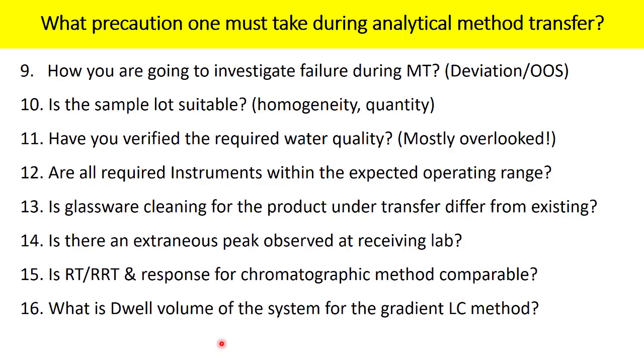And last but not the least. In case if you are operating on the gradient elution mode, the dwell volume or gradient delay volume is very critical to get the expected chromatographic pattern. And sometimes your analytical test procedure may say that you can have some change in the flow based on to the dwell volume. So ask for the dwell volume. How much is the dwell volume of your system during the analysis? And then compare in the QC. What is the dwell volume of your HPLC system? If there is a great difference between dwell volume, you may end up getting the different chromatographic pattern, different retention times. So the correction may be required.